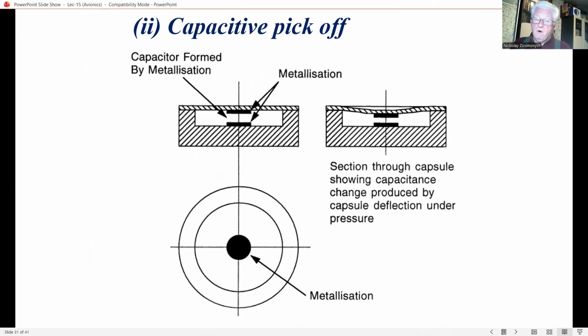The capacitive pick-off and bridge configuration must be designed so that it is not affected by changes in the stray capacitance inherent in the lead-out wire and screen, as these changes can become variable or even exceed the very small changes due to the input pressure. A precision A to D conversion is required to provide the required digital output.